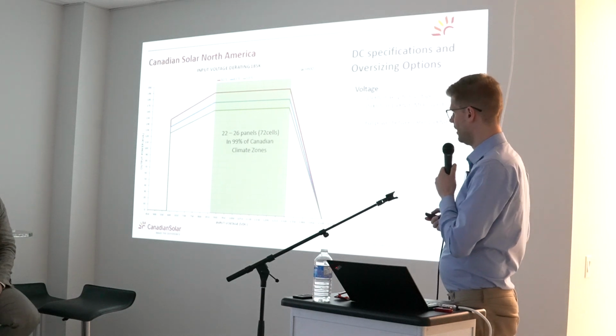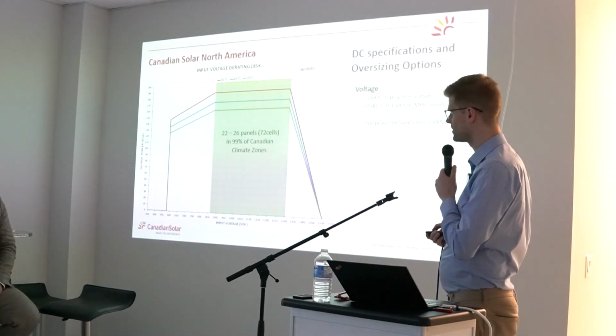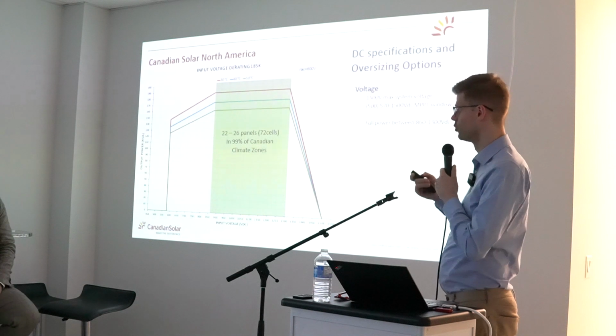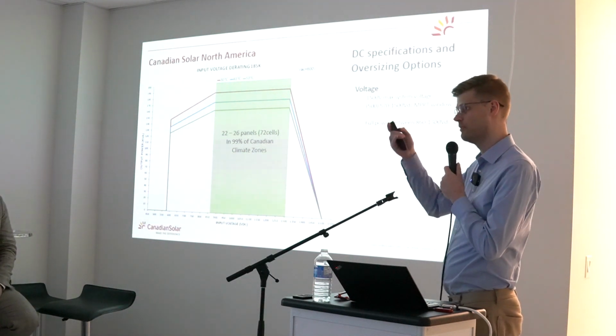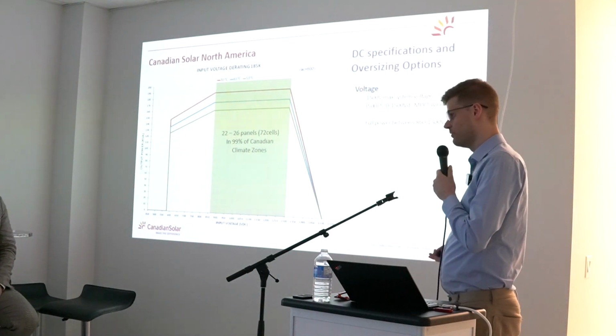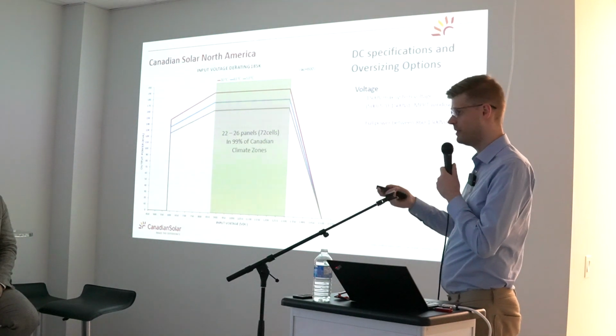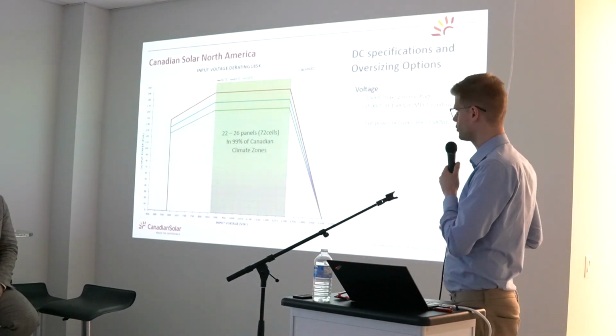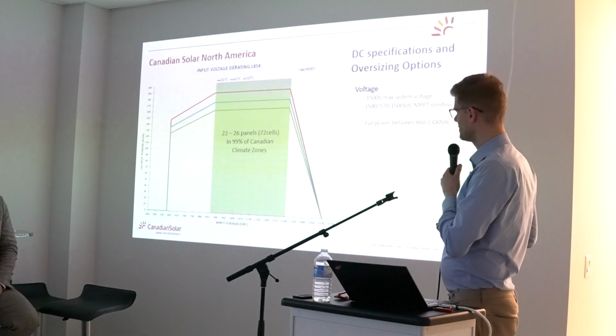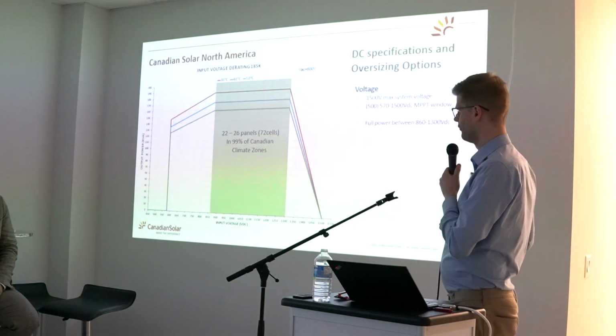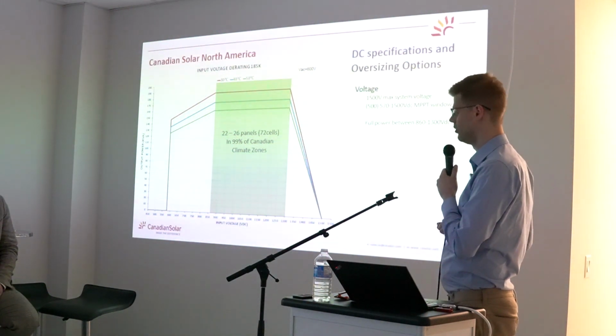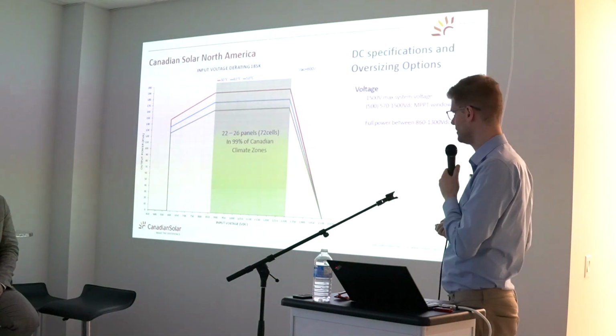On the DC side as well, you see, as with most string inverters that are a dual stage concept, that you have a boost converter and then a buck converter. So boost converter on the input for the MPP tracker and then the buck mode on the actual output stage. These systems are typically 1,500 volt systems. So the maximum voltage can go all the way up to 1,500.